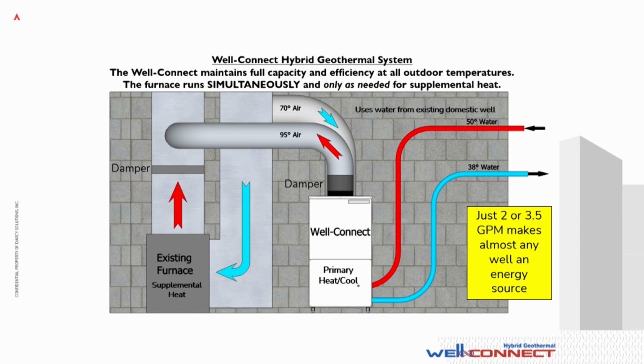And that combination of those two things, and because it's an add-on system, we only need 2 gallons a minute for our 1.5 ton and 3.5 gallons a minute for our 2.5 ton total. So it's not 2 gallons per ton, it's 2 gallons total, or 3.5 total. And it's a rare well, at least in Michigan, that cannot handle that. So 90+% of the wells that we have are candidates now to be a free, clean, renewable energy source for that homeowner, and it's already sitting right there in their yard.